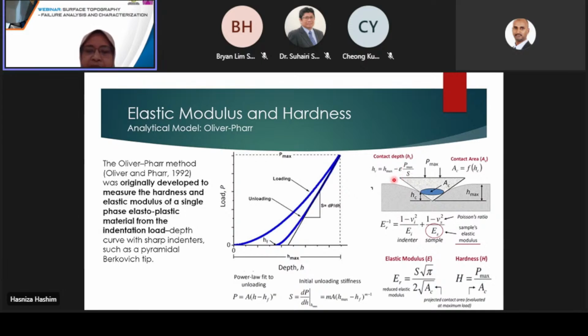HC, the contact depth, is equal to the max depth minus the max force times epsilon, which is some geometric constant depending on the indenter tip installed, divided by the stiffness. The modulus measured in nano indentation is specifically called reduced modulus, or ER. The relationship between reduced modulus and the Poisson ratio of our indenter, in our case a diamond probe, and the unknown modulus and unknown Poisson ratio of a sample is shown via this expression.